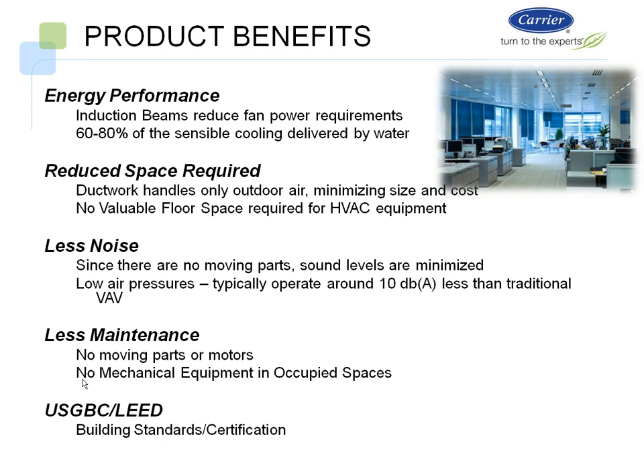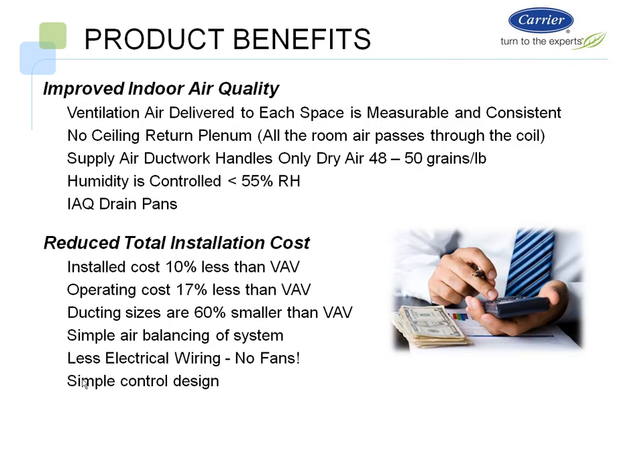And again, if you're installing it with condensate as well, there's things you can even do with the condensate. There have been examples for LEED-type buildings where they take that condensate and treat it, and then use that for watering a garden or for watering the plants or shrubbery of the same building, and grab some more LEED points as well. So again, improving the indoor air quality. Again, the ventilation is delivered to each space and is measured. Basically, what's going into that space is what's designed for that space.